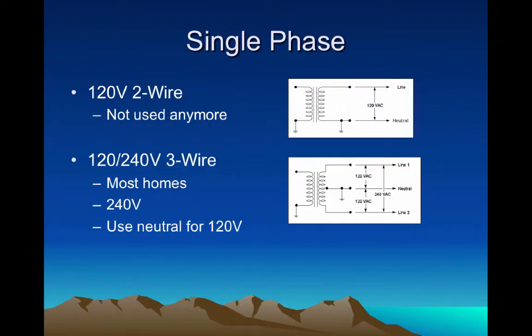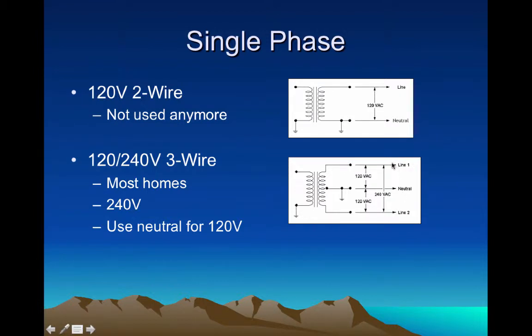When it reaches our house, the power company will typically land only one leg of that power to our homes. The most common is our 120/240 volt three-wire system, which is in most of our homes. Really what's coming into our homes is 240 volts, but when we add the neutral we can derive 120 volts. Or you can use a larger power outlet — for dryers, air conditioning units, electric ovens or stoves — going between the ends of the phase to get your 240 volt outlets.